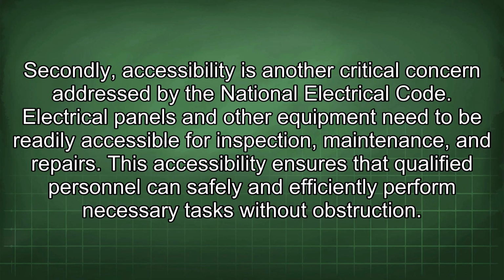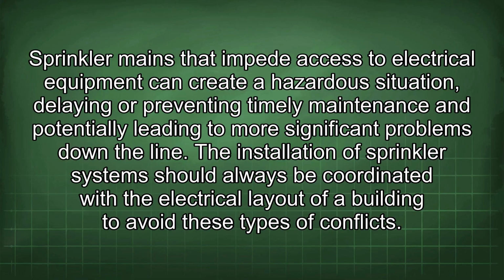Secondly, accessibility is another critical concern addressed by the National Electrical Code. Electrical panels and other equipment need to be readily accessible for inspection, maintenance, and repairs. This accessibility ensures that qualified personnel can safely and efficiently perform necessary tasks without obstruction. Sprinkler mains that impede access to electrical equipment can create a hazardous situation, delaying or preventing timely maintenance and potentially leading to more significant problems down the line.